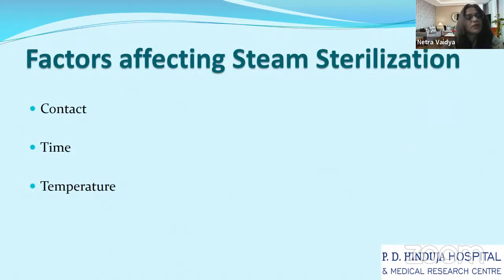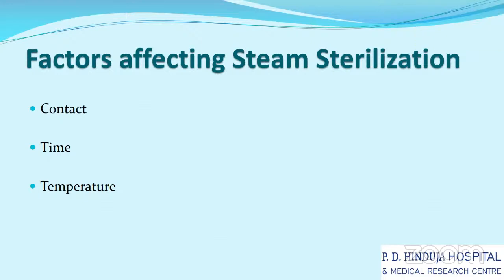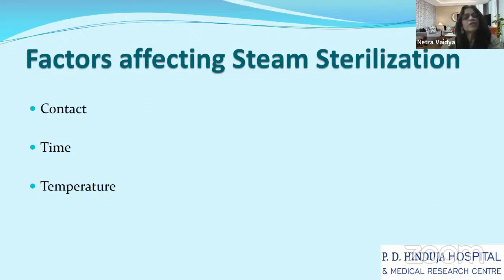Now, these are the three main factors: your contact time, your time for sterilization, and your temperature. In steam sterilization, we widely use two temperatures: one is 121 and the other is 132 or 134 degrees. The time for sterilization depends on the temperature. The lower the temperature, the higher the time required; the higher the temperature, the lower the time required. And your contact time depends on what you are sterilizing, so you need to get your IFUs clear, and then you can decide on the time factor.